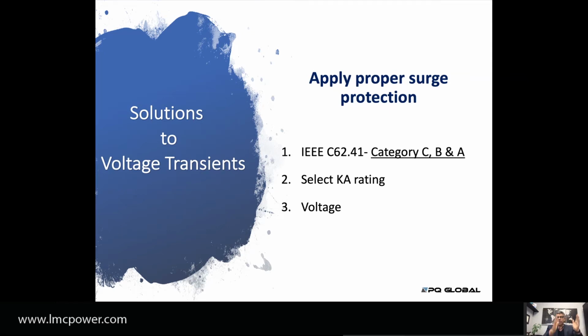Is this electrical panel that we're protecting at the entrance of the building category C, at least 150 kA, and it's 480/277? That's all I need to specify my surge protection for that site, that location. Category B, 100 kA, 208/120. That's all I need to be able to recommend the right surge protector for that location, okay?